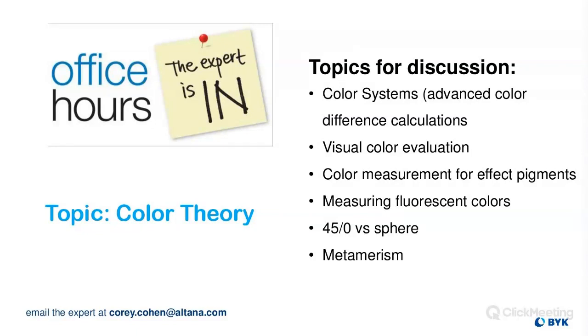So if you might be using an instrument with a tungsten bulb that has very low emission in the blue range, those percent reflectance measurements you'll get in that range aren't going to be perhaps as precise as you might get with a light source that has more power in that range. So it doesn't really matter what the spectrum is. You just need to be able to see enough power at every wavelength.